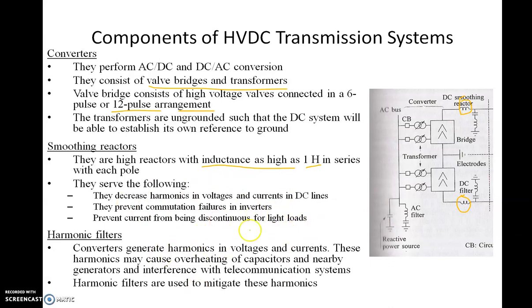Smoothing reactors also prevent commutation failure in inverters. When we use thyristors or SCRs, we have to turn off the switch — turning off the switch is called commutation. Just like turning on a fan switch is called firing, turning it off is called commutating. Commutation in these converters is automatic or based on the control system, but sometimes commutation failure can occur. This is a major problem that can be prevented by using the smoothing reactor.